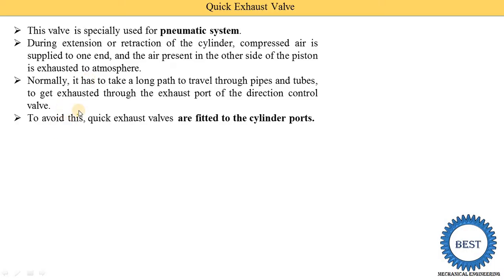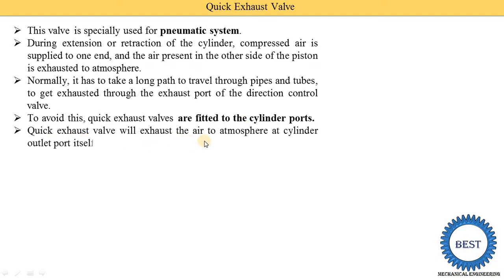In a pneumatic system, air coming out from the rod end port travels through pipes and tubes to the directional control valve — this is a very long path. To avoid this, quick exhaust valves are fitted to the cylinder ports. The air coming out from the rod end port is not sent back to the directional control valve. Instead, the quick exhaust valve exhausts the air to atmosphere at the cylinder outlet port itself, avoiding the need to travel a long distance.